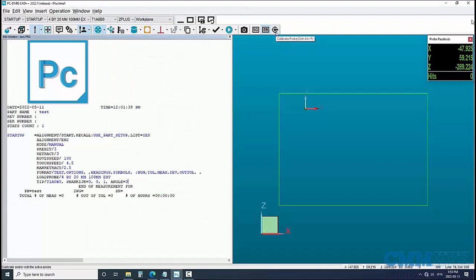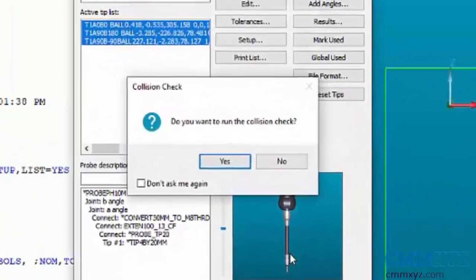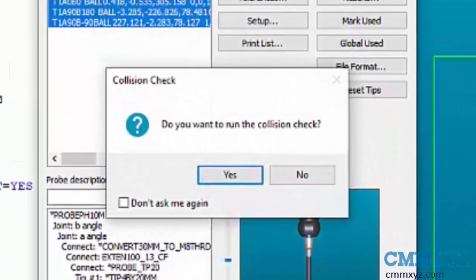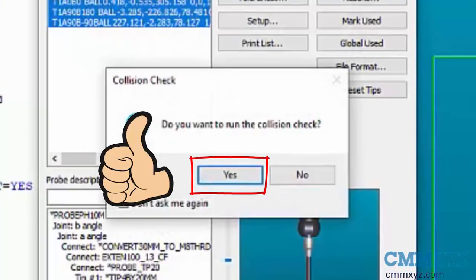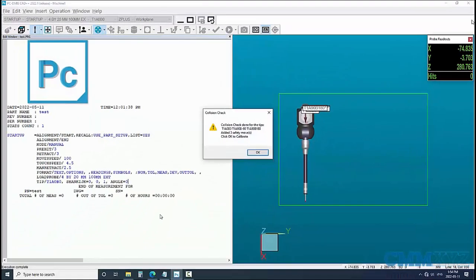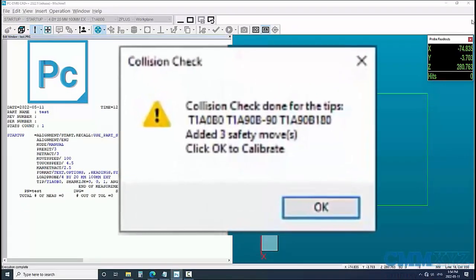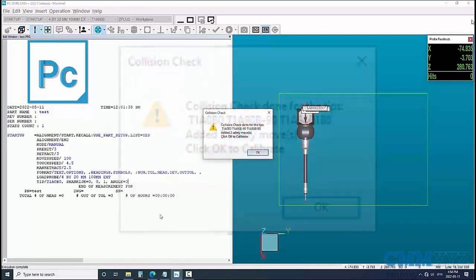Let's go ahead and launch our probe calibration. Here's the first new prompt: 'Do you want to run the collision check?' I'll answer yes and we'll see what's next. PC-DMIS has run a quick mini collision check in the background and reported its findings. In my case it needed to add three safety moves, so it should be safe to calibrate now. Go ahead and click OK and launch the calibration.